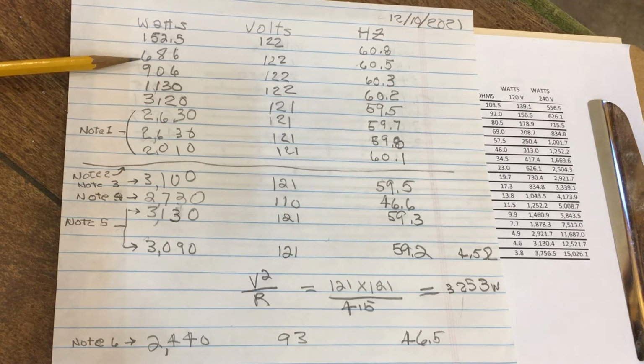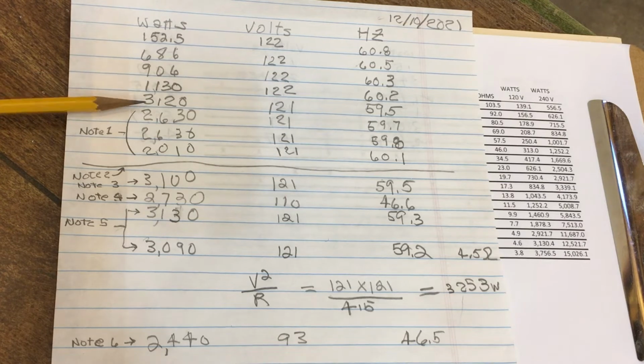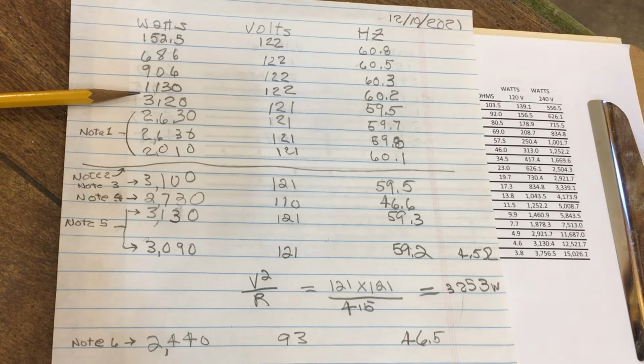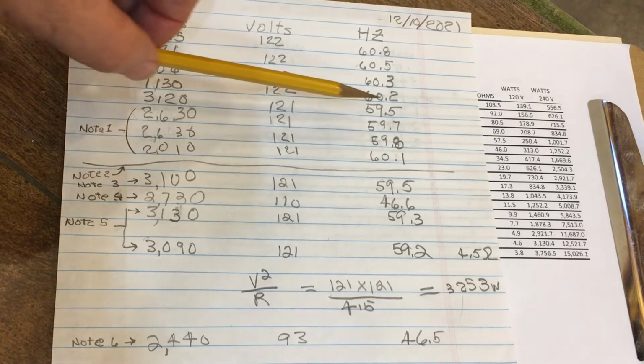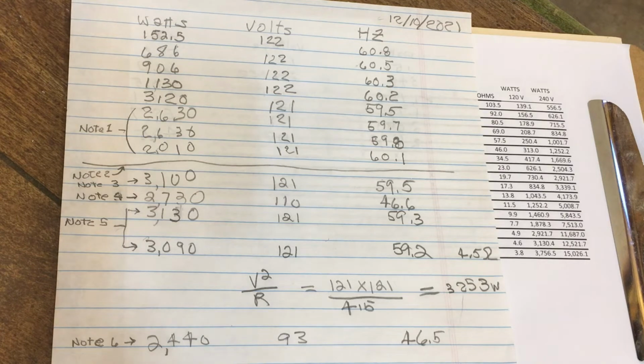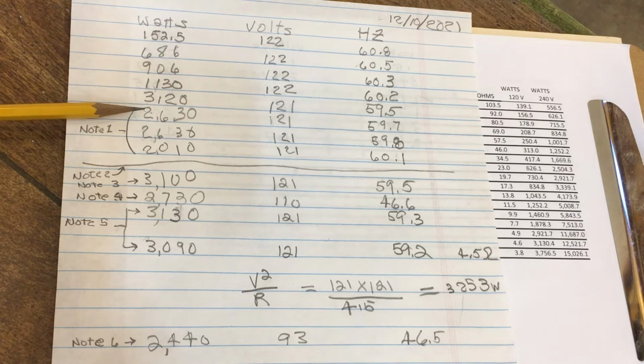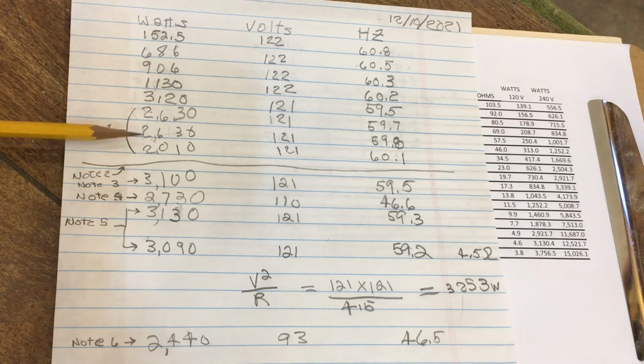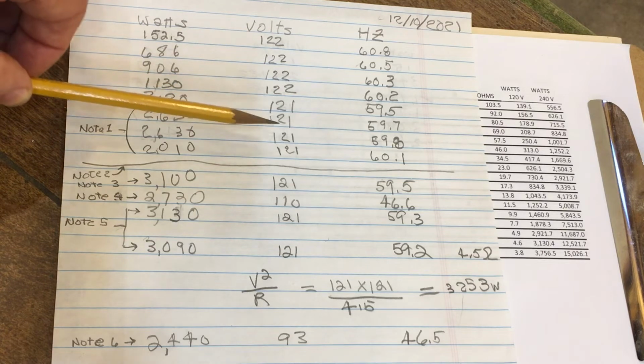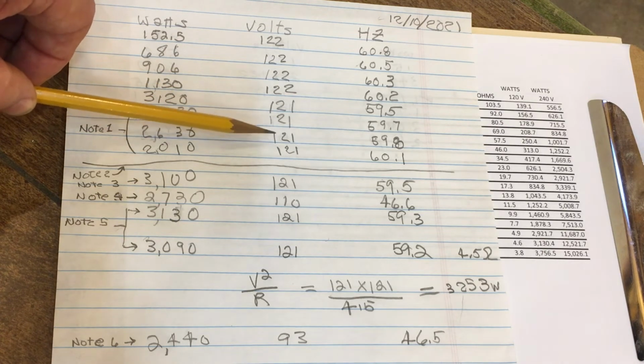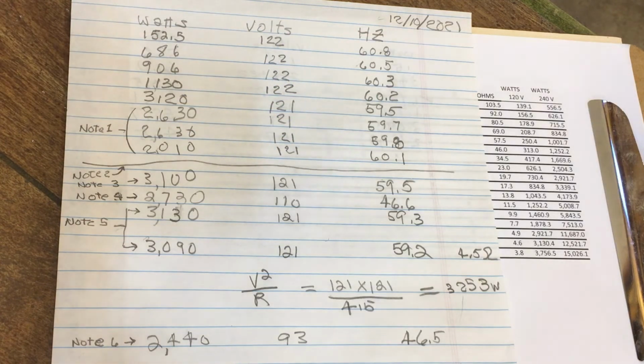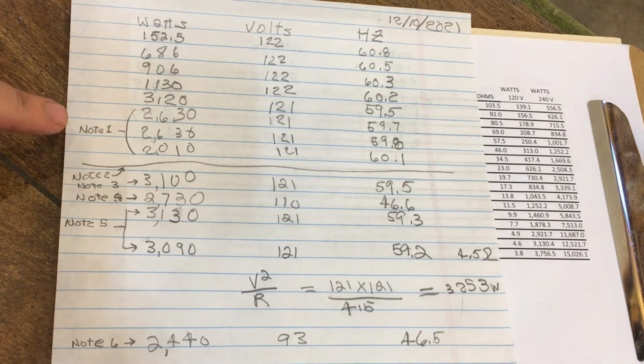Everything was looking very good, and the load keeps increasing till we get to this point at 3,120 watts. Still the voltage looks good. Frequency is very reasonable, 59.5 hertz. And then the next step, I was attempting to increase the load, but as you see, it didn't change. It actually went down from the previous line. In the next 3 lines, I was changing switch settings, but I wasn't getting any increased load. And then I began to realize that as I recorded, the voltage was staying up, the frequency was staying up. Basically, I had a failure in my load bank, and at that point, I realized I couldn't go forward.